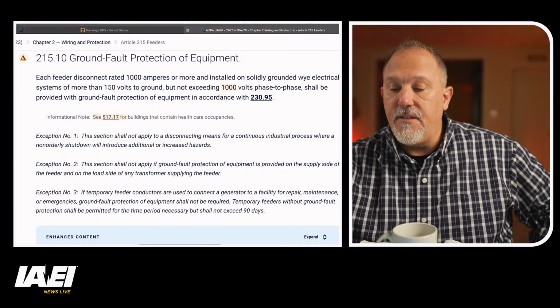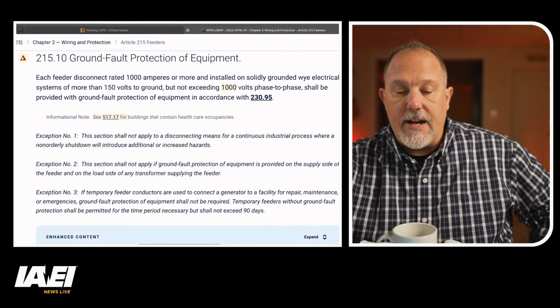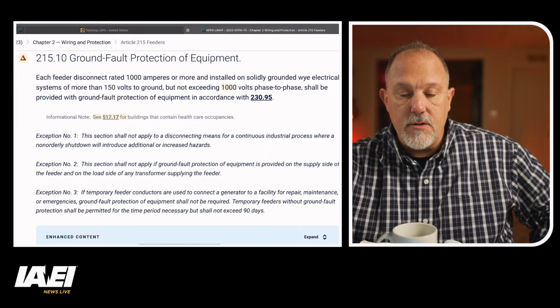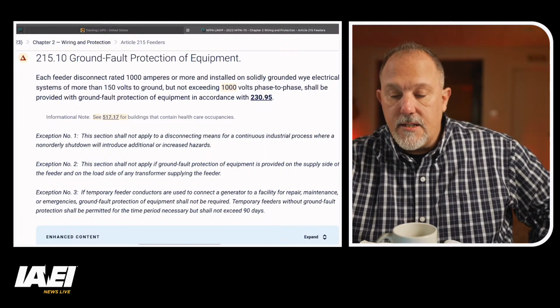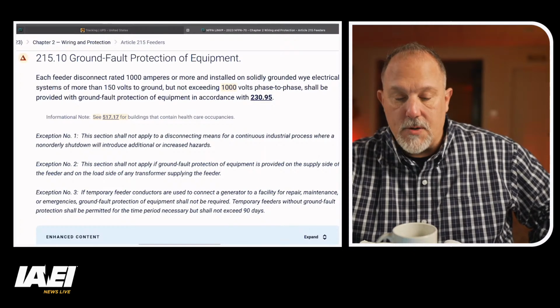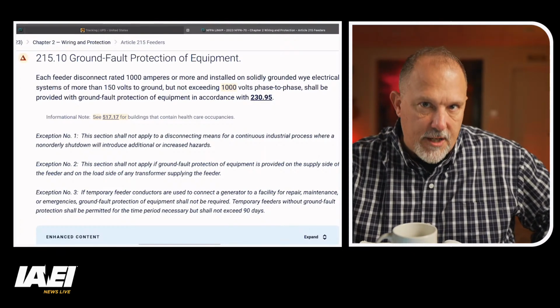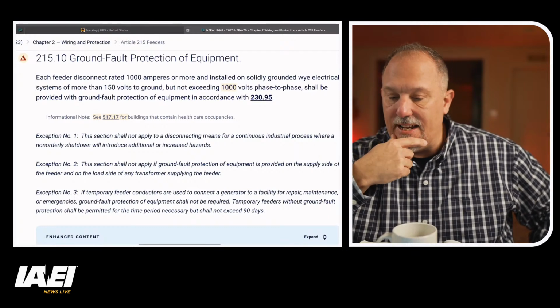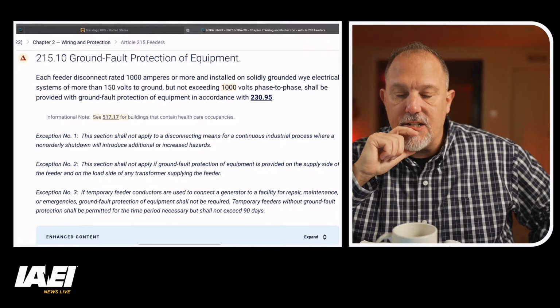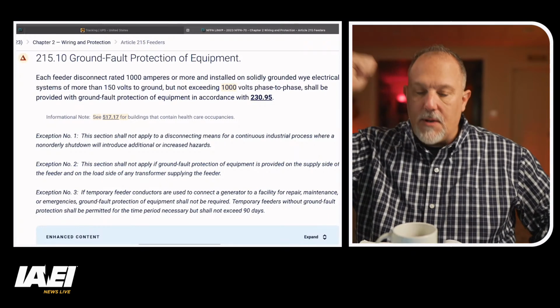And then we have 215.10. It says each feeder disconnect rated 1,000 amps or more and installed on solidly grounded wye electrical systems of more than 150 volts to ground, but not exceeding 1,000 volts phase to phase, has to be provided with ground fault protection of equipment. There is an informational note, and there are three exceptions. It doesn't apply to a disconnecting means for a continuous industrial process where a non-orderly shutdown can introduce additional or increased hazards. Exception number 2 is that the section is not applicable if ground fault protection of equipment is provided on the supply side of the feeder.